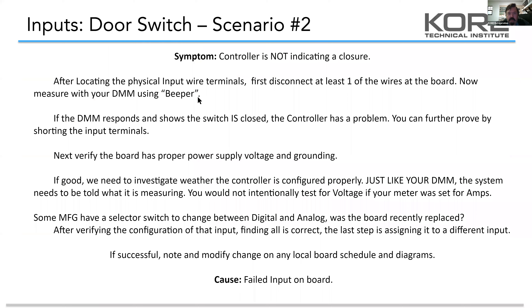Here's another scenario. After locating the physical input wires, let's say we're not getting a magnetic closure indication and the door closure is not being indicated. We're going to do the same thing — second-guess what the controller is seeing and check for continuity. This time, the digital multimeter responds and shows the switch is closed, yet the controller is having a problem. So now we want to take control of what we're doing with the controller. We see that the actual continuity on our meter is good, but the board for some reason is not reading the system.